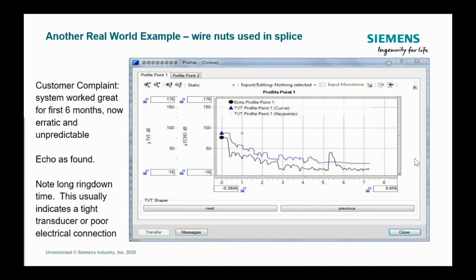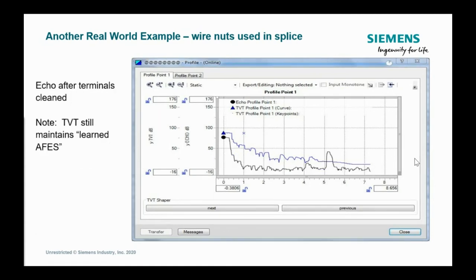And so we go back to the transducer, and we trace back from the transducer, and a couple of LB condulets later, pulled the cover off. Voila, there are your three yellow wire nuts. And I went, here's the problem. Pull the three yellow wire nuts off, cleaned up the connections, and tightened them back, and came back, and boom, look at the difference. And I'll toggle back and forth between the two.